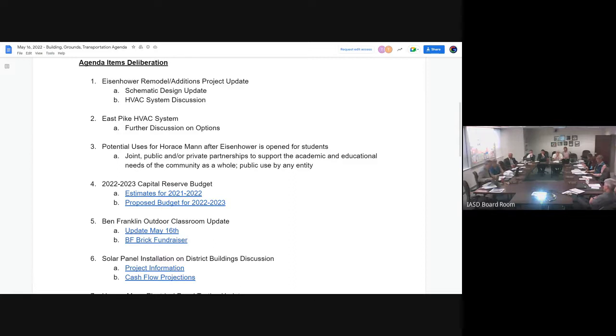Yeah, but a couple of questions I had was, you had 1 unit, 1 closet, 1 unit serving the copy room and the outside services room. There's 2 different needs there. Right. How's that going to function? You're going to pick a middle ground. Not middle, ideal. Now, you could flip this, and this would be a good place for your cassette system, a small cassette system, just in those two rooms. Right. Because those two rooms are different, but it doesn't make sense to do one of these heat pump units for each one.